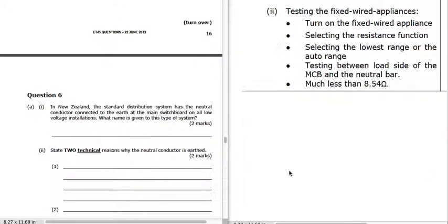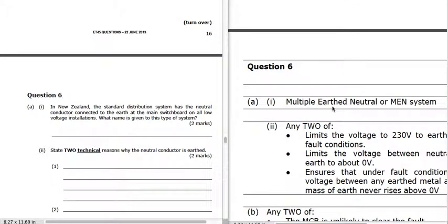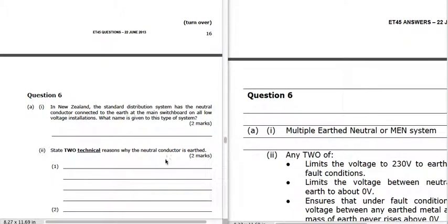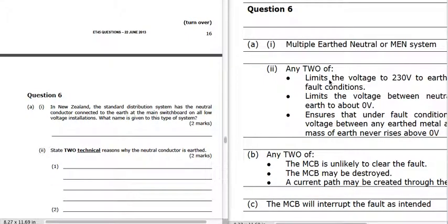Question 6: in New Zealand the standard distribution system has the neutral earthed — this is called the multiple earthed neutral, or MEN system. Two technical reasons why the neutral conductor is earthed: it limits the voltage to 230 V to earth under fault conditions, and it limits the voltage between neutral and earth to about 0 volts. It also ensures that under fault conditions the voltage between any earthed metalwork and the mass of earth never rises above 0 volts. These are things you must know going into the test — they come up again and again.